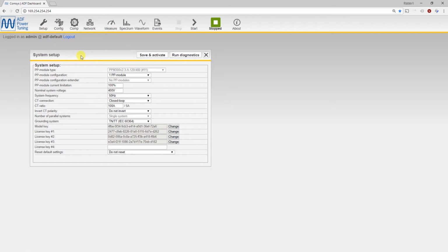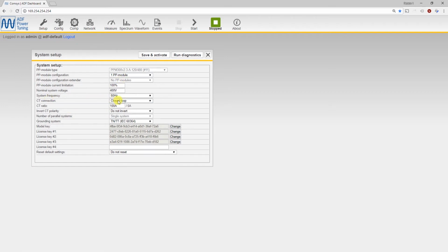If we open the web interface and look in the setup window, we have here the CT connection. We can have closed loop, open loop or no CTs. You can still connect CTs and run it in closed loop, still operate the active filter in sensorless. What you need for sensorless is one of the license keys. So just make sure you get a license key from Comsys and then you'll be able to run it sensorless. We're going to keep the CTs on here right now. There are some CTs connected, so we will also see a little bit of current running here.